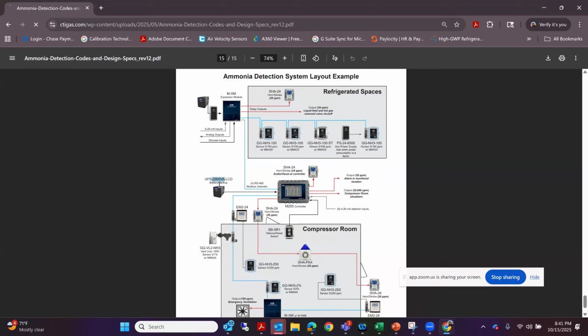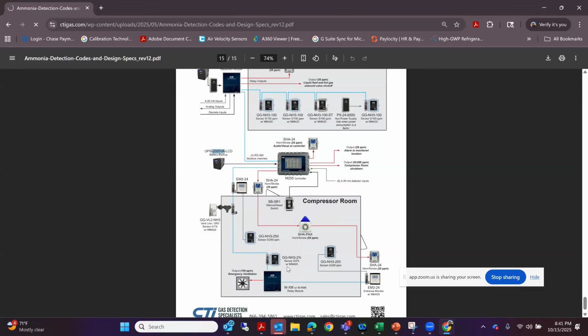And so what I've always told everybody is that it makes sense to have a generator, because number one, if you're not sheltering in place, and we're going to leave ventilation running, if power goes out, ventilation is supposed to be on that same generator circuit. It's got to keep the fans moving, because we can't have that buildup of ammonia inside the compressor room, right? So the fans were always supposed to be, in my understanding, backed up and still running, in order to keep the ammonia from building up inside the compressor room, because it's really, really hard at 20 or 30 air exchanges to even get over 15,000 ppm in here, is my understanding. And so when you're moving that much air, you're always going to be safe, right?